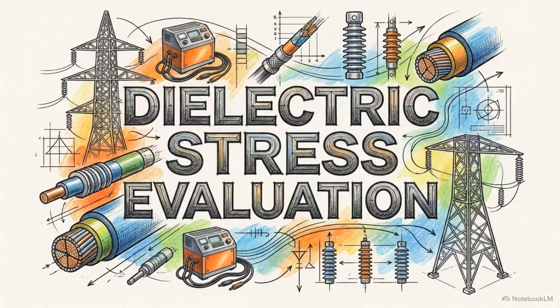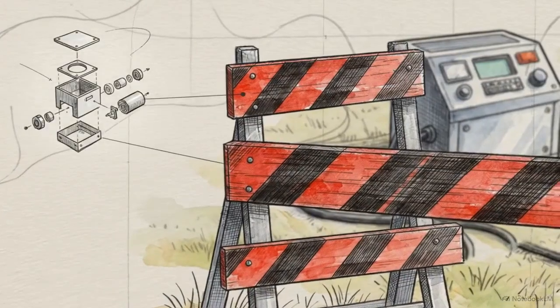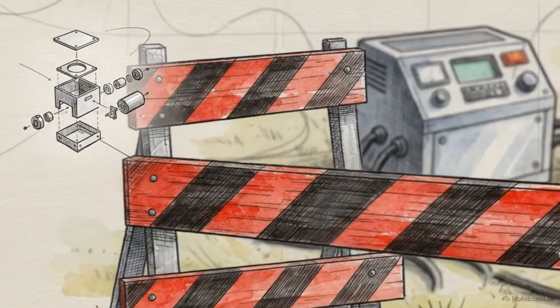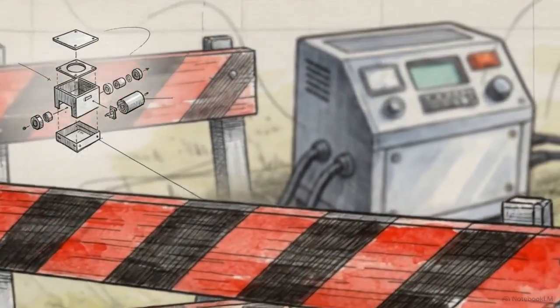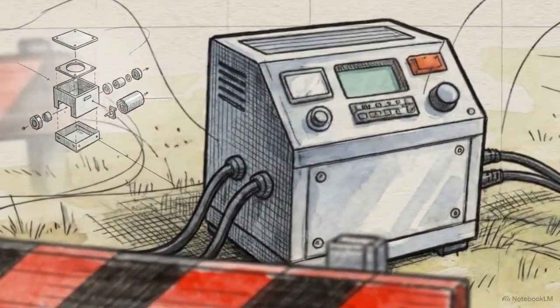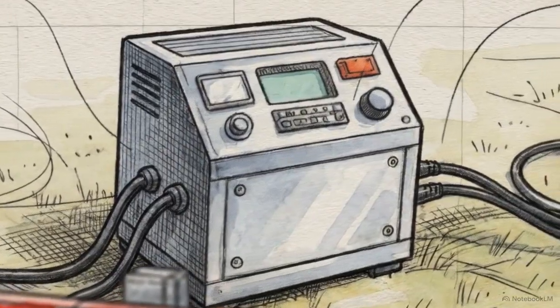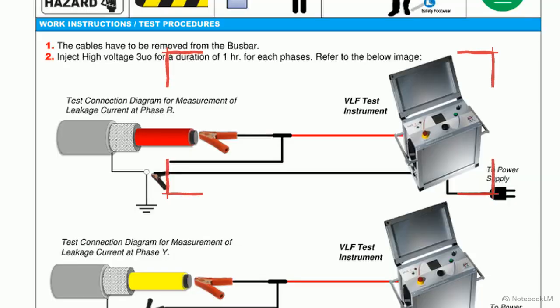Test 13-7 is the power cable very low frequency high voltage test. Because this applies extreme dielectric stress, it requires setting up a remote exclusion zone with physical barricades and warning signage around the VLF test instrument. This diagram shows the VLF connection.